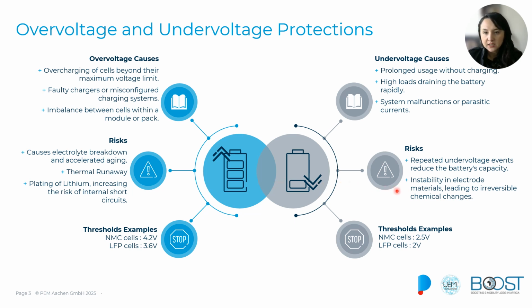These conditions will cause, for instance, instability in the electrode materials that can lead to irreversible chemical damage, and as well it can lead, for instance, to reduced battery capacity and reduced battery health when we use the battery at very low voltages. The BMS also protects against the under voltage by disconnecting the load when any cell is approaching its lower voltage threshold, and again this threshold will change depending on the battery cell and the chemistry, and also the specifications of each cell will provide us what these safe limits are, both on the upper side and on the lower side of it.